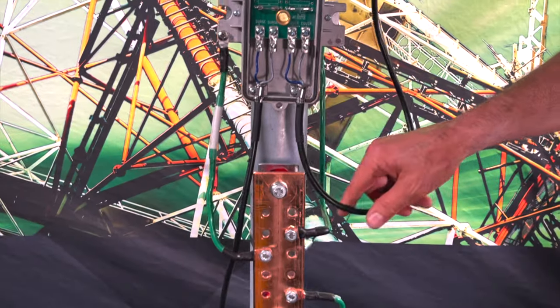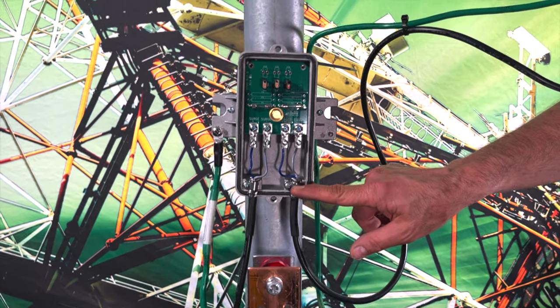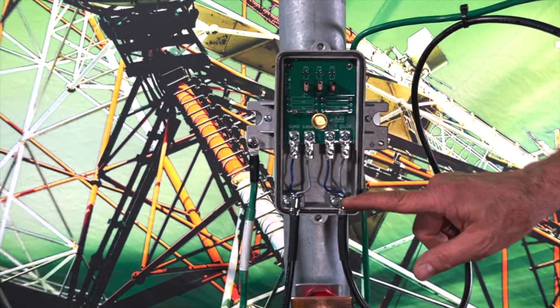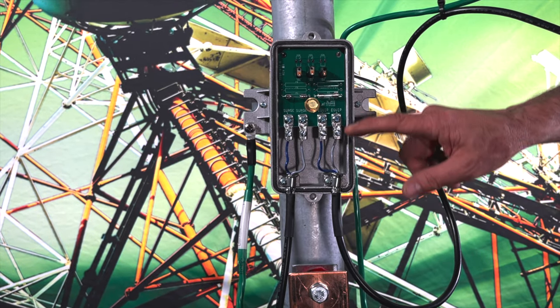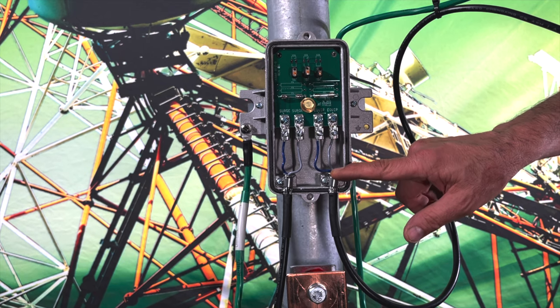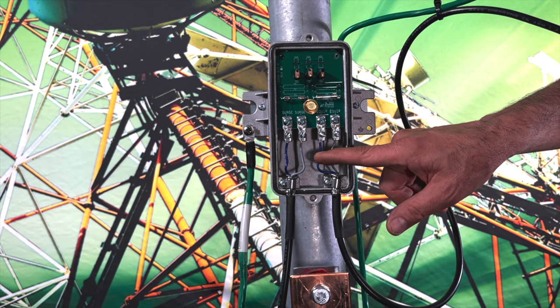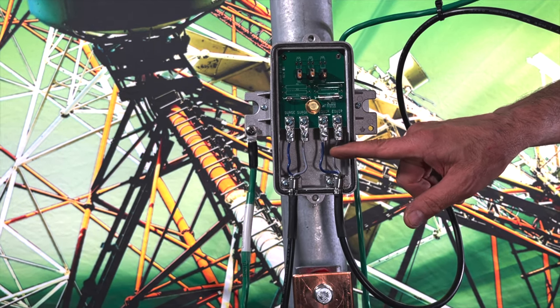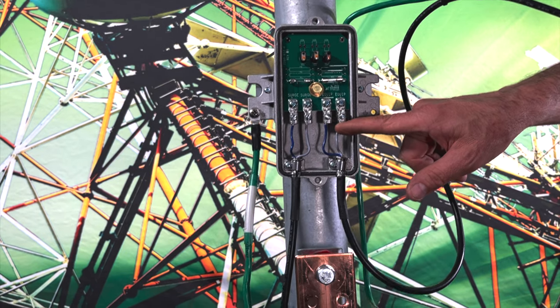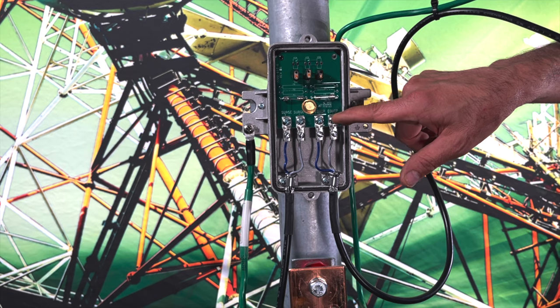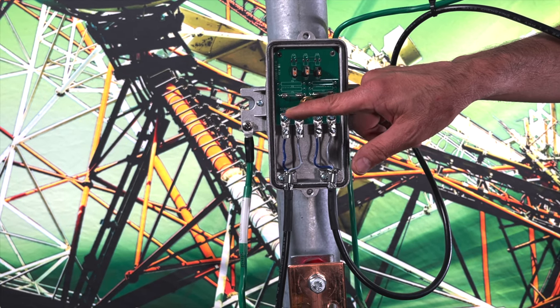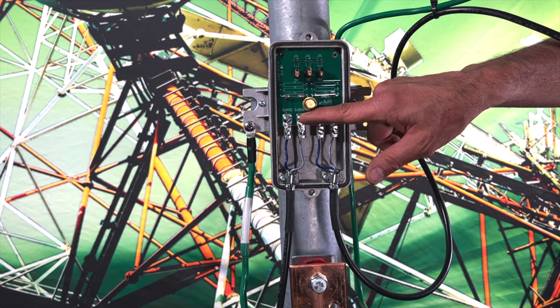Now, our DC power wire, you'll notice here under this clamp, this is where our braid is. This is what is grounding the cable to the earth ground to the chassis of our surge arrestor. We've elected to use blue for our positive and gray for negative. As you put in your two conductors into the terminals here, you want to pay attention. They're labeled positive and negative. Same thing on this side, on the surge side, the positive and the negative.